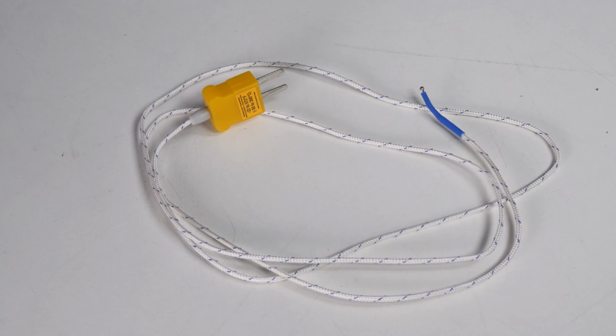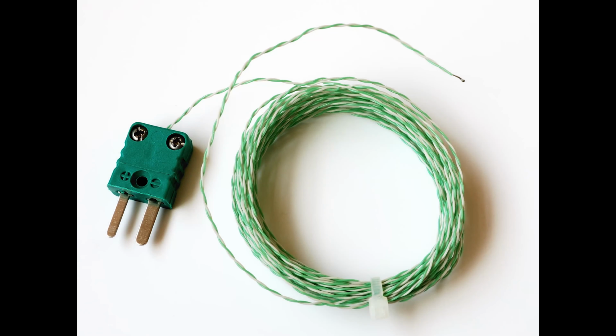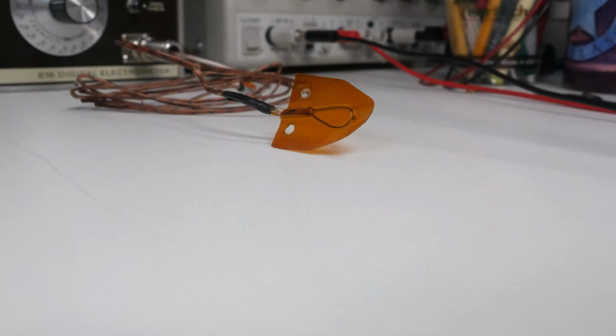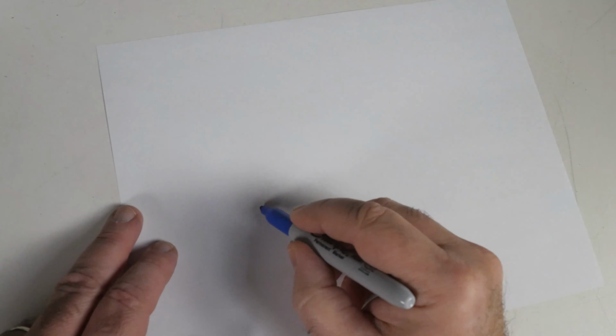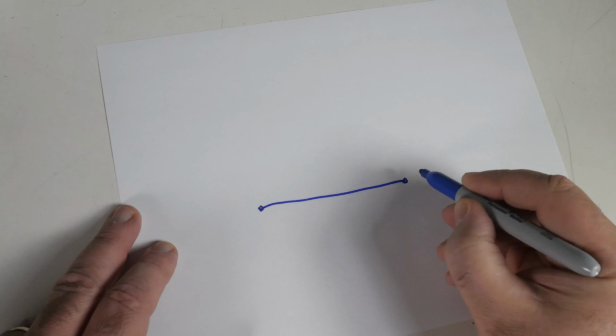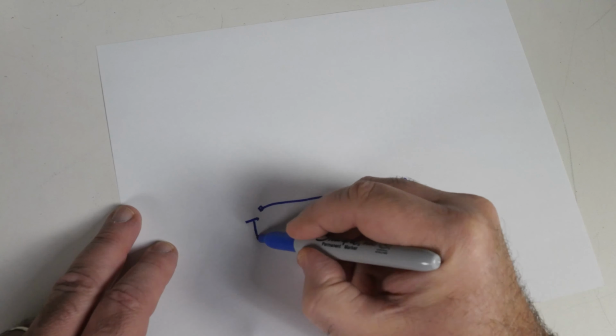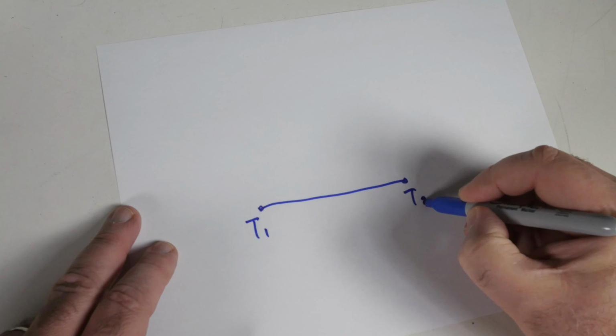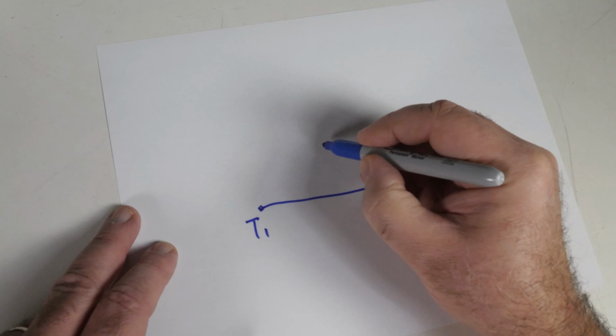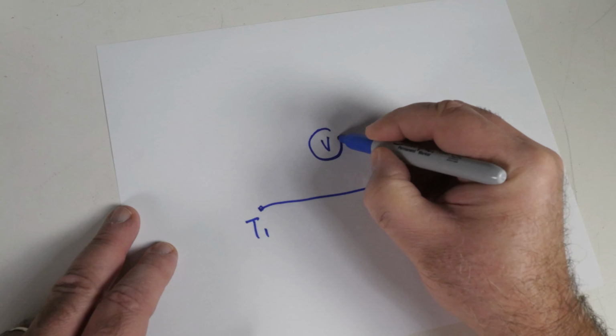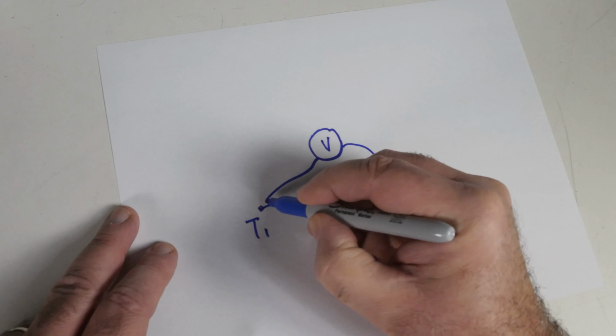Thermocouples are widely used for temperature measurement. They are cheap and work across a wide temperature range. The operation of the thermocouple is based on the Seebeck effect. The Seebeck effect refers to the development of a voltage across 2 points of an electrically conducting material when there is a temperature difference between those 2 points.